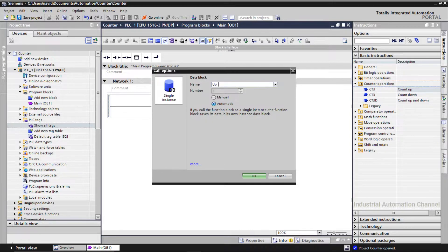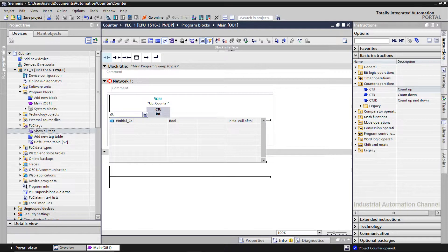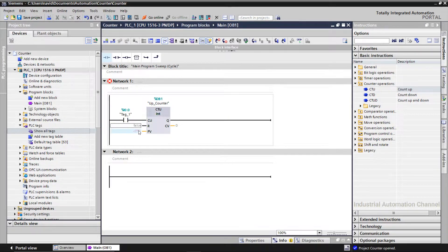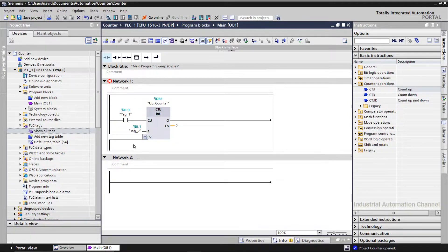Determine a name for the counter and hit OK. This counter counts up by 1 when the signal state at the input parameter changes from 0 to 1. So when the input CU detects a positive signal, the current counter value at CV will be incremented by 1. I insert a normal contact as counter input I0.0. We also have a reset input — if we give a signal here the current value will be 0. PV or preset value is the upper limit for incrementing the current value and determining the signal state at the output.